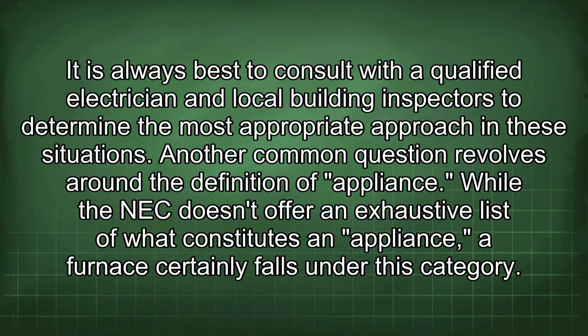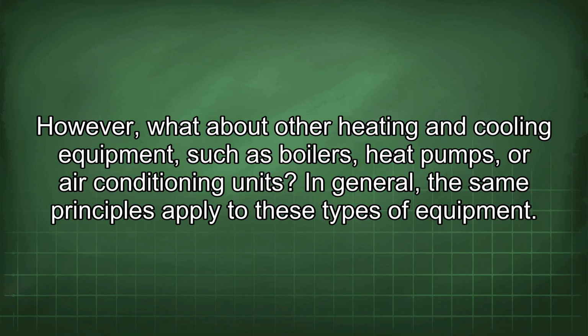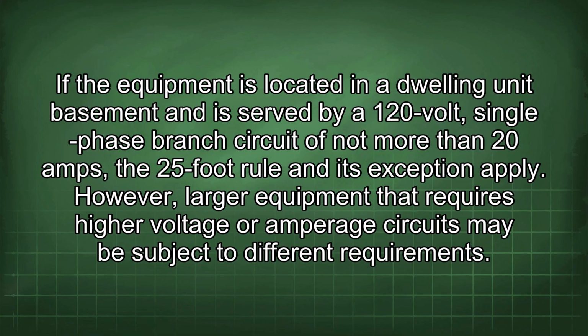Another common question revolves around the definition of appliance. While the NEC doesn't offer an exhaustive list of what constitutes an appliance, a furnace certainly falls under this category. However, what about other heating and cooling equipment, such as boilers, heat pumps, or air conditioning units? In general, the same principles apply to these types of equipment. If the equipment is located in a dwelling unit basement and is served by a 120-volt single-phase branch circuit of not more than 20 amps, the 25-foot rule and its exception apply. However, larger equipment that requires higher voltage or amperage circuits may be subject to different requirements.